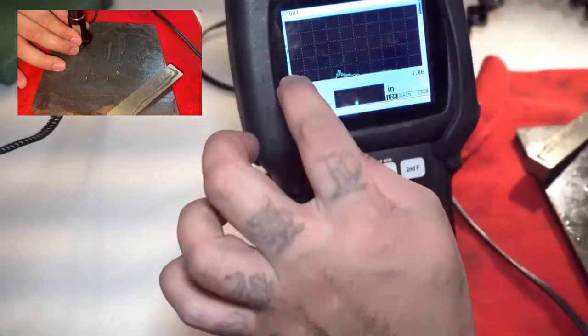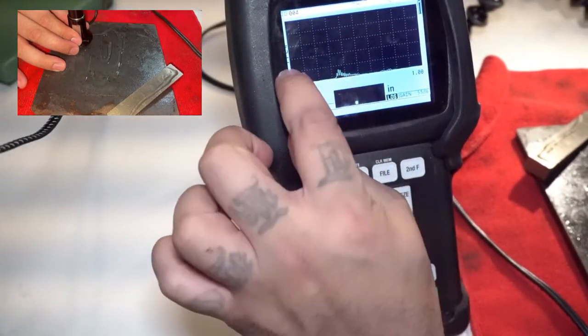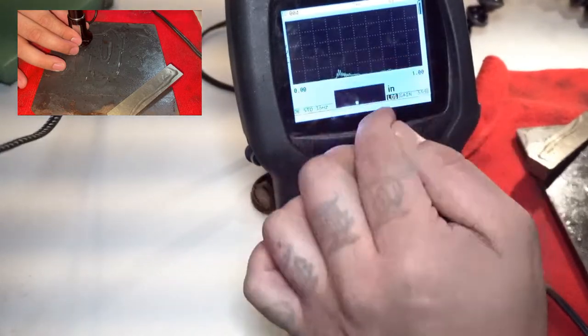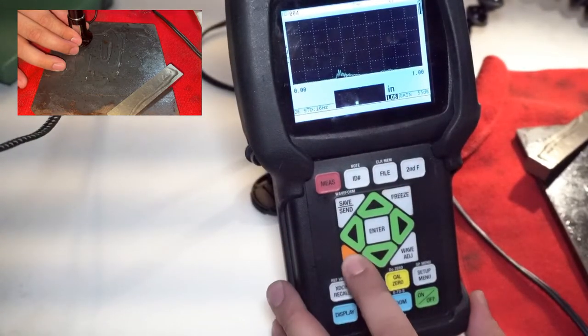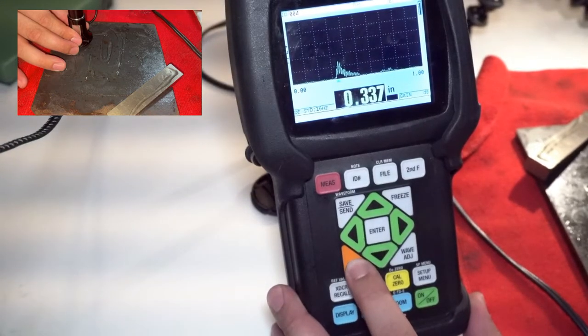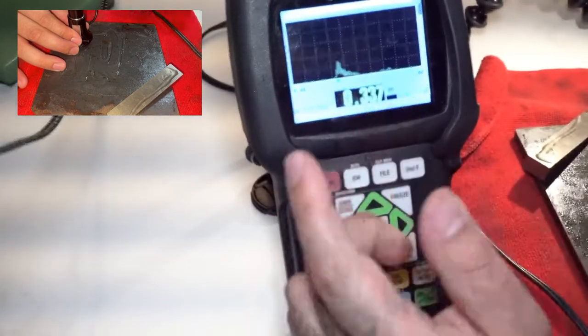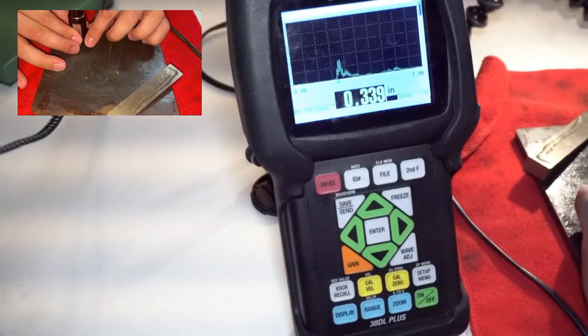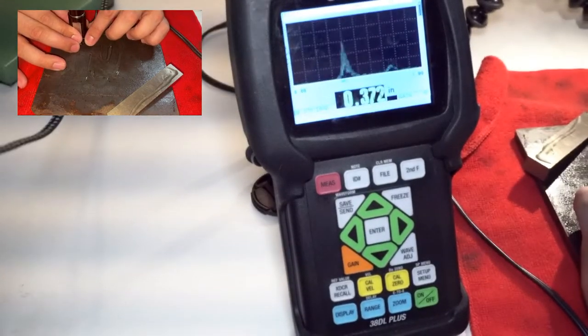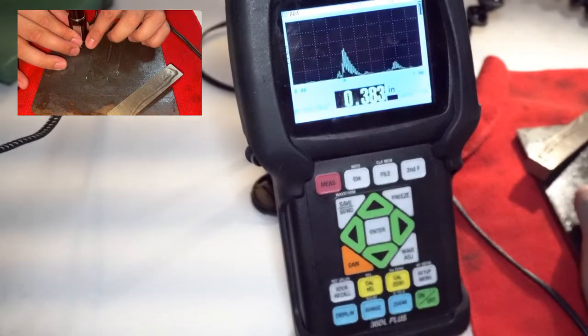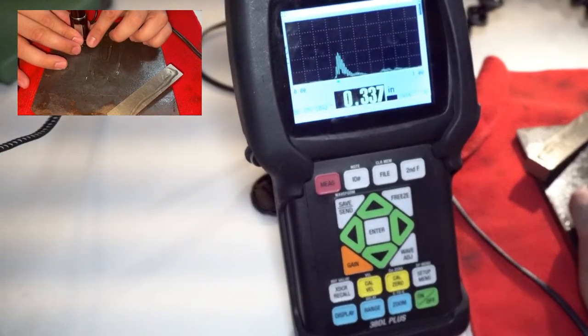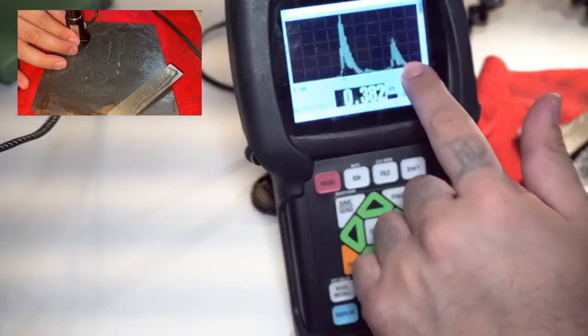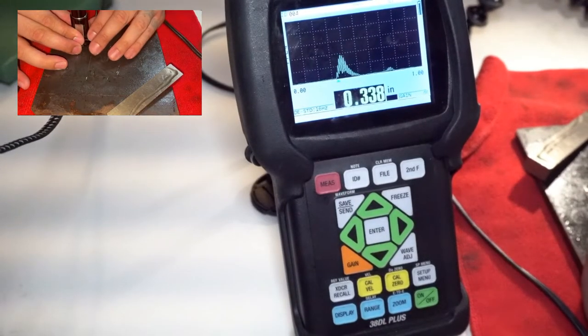The reason for that is my signal has to be above 20% in order for the unit to recognize it. So at this point, I'm going to increase that gain back up here. Now it's above 20%. It identifies the signal and says, hey, this area here is about 337. So we see it shift, move over. The other thing that you notice is the second back wall is completely gone. See that.